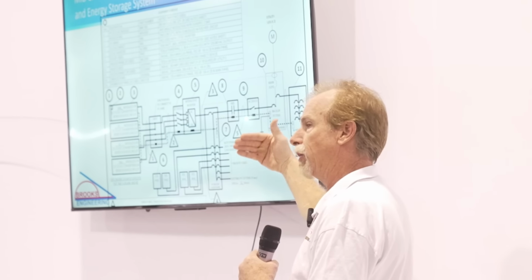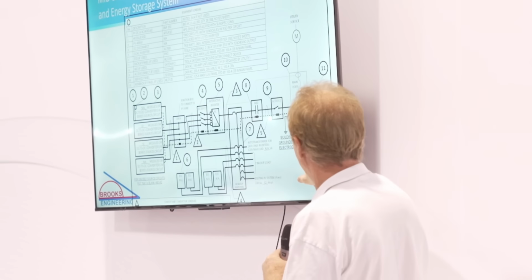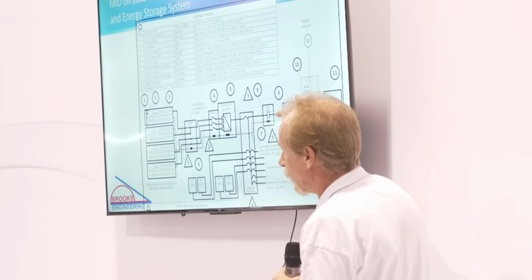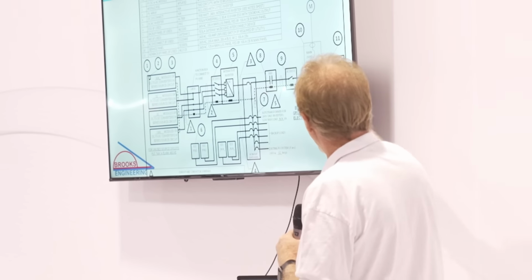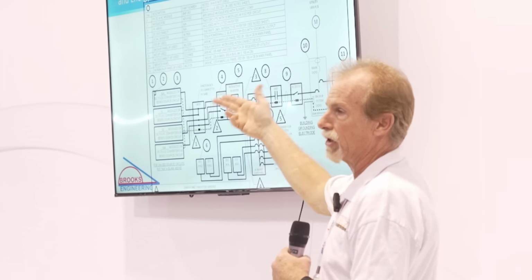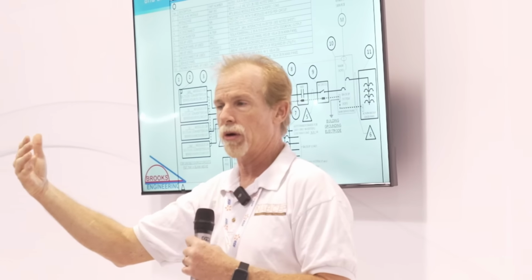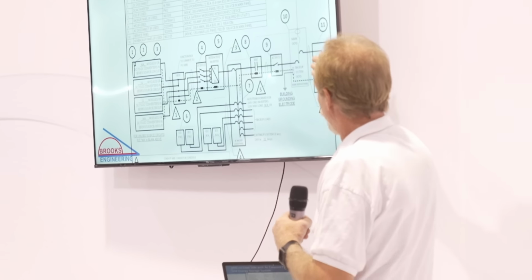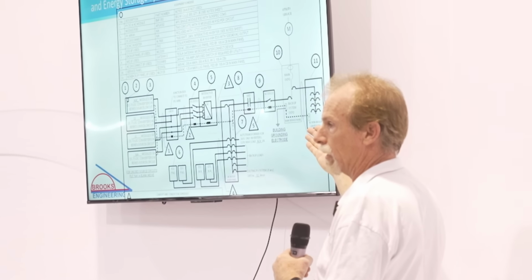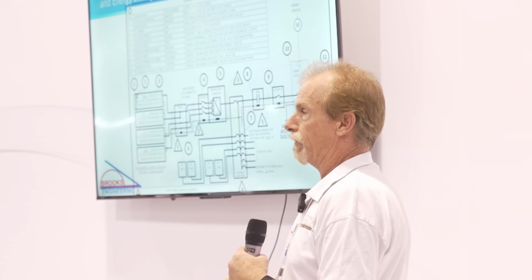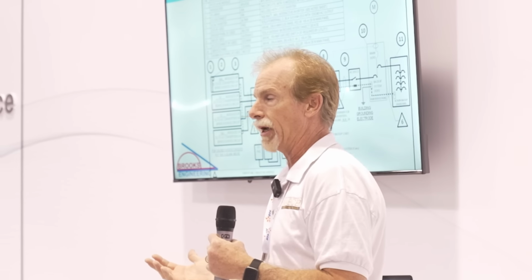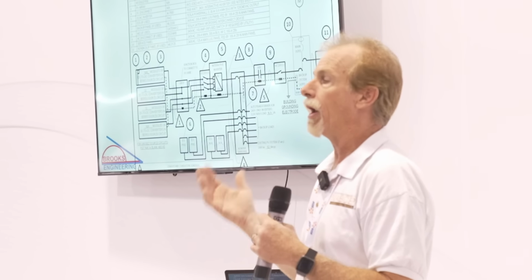Okay, so we're trying to use the sum of the breakers rule. The sum of the breakers rule says 100 plus 100, you're already up to 200. So if you have a whole bunch of small breakers in there, that's going to take you over 200. That's why if we're going to do it this way, we've got to pull it out and put it in a separate box. Now, from a physics point of view, does it make much difference? Probably not.